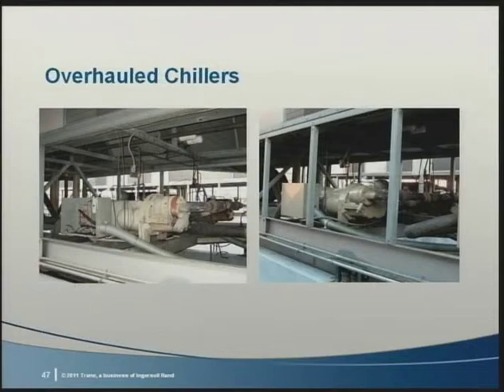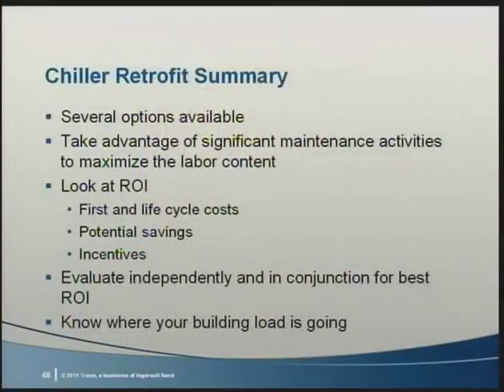So for example, at a data center in the Pacific Northwest, they systematically overhauled all their screw chillers and are saving 4% on their chiller energy cost. These savings have been verified by the local utility company. In summary, there are a variety of chiller upgrade opportunities that should be evaluated as part of your study. Take advantage of maintenance activities when you're making these changes, when you're already applying the labor.